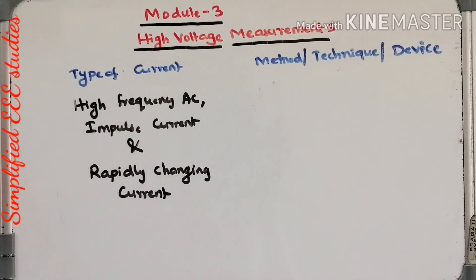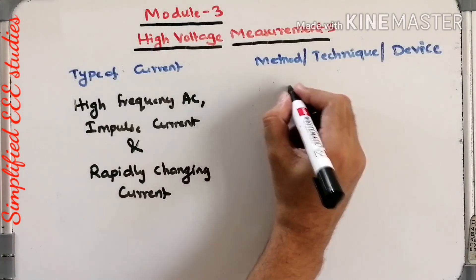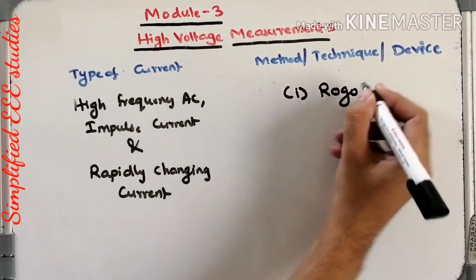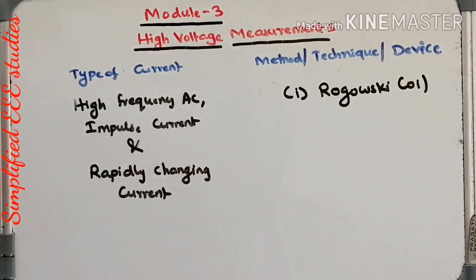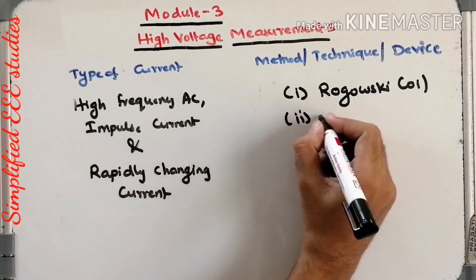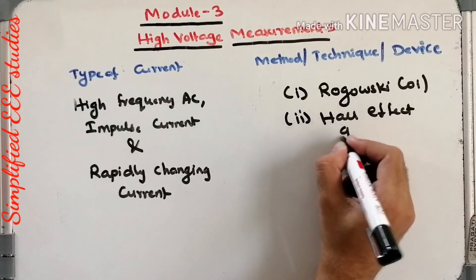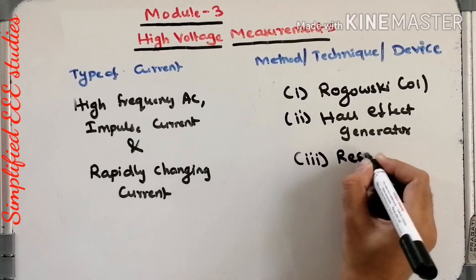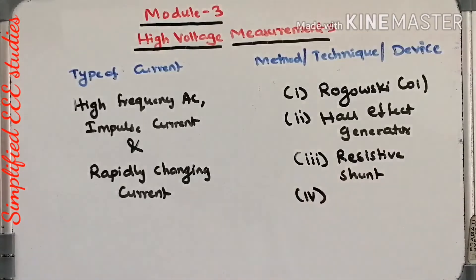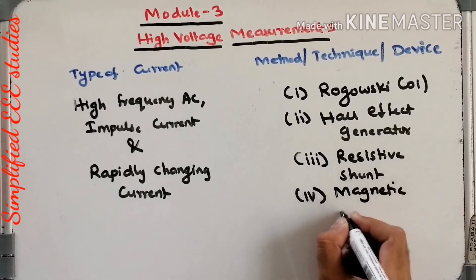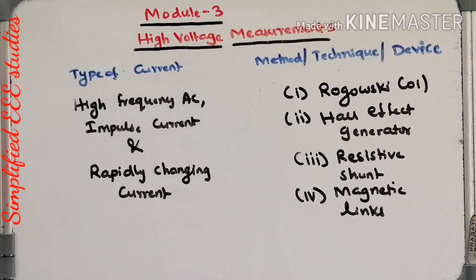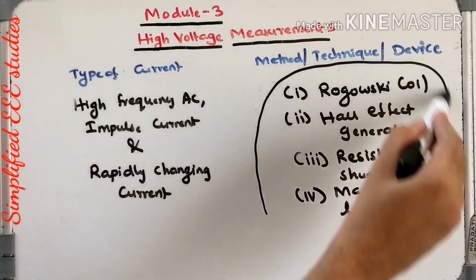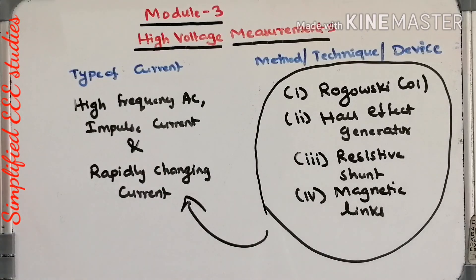For measurement of high frequency AC, impulse current, and rapidly changing current, the available devices are: the Rogowski coil, which works on the principle of mutual induction; the Hall effect generator; a resistive shunt; and magnetic links, which work on the principle of remanent magnetism.